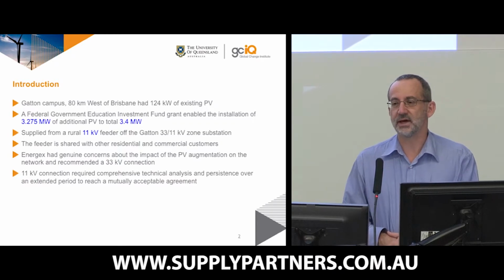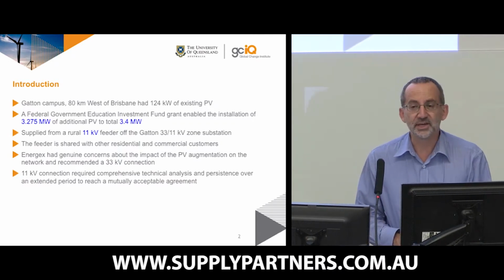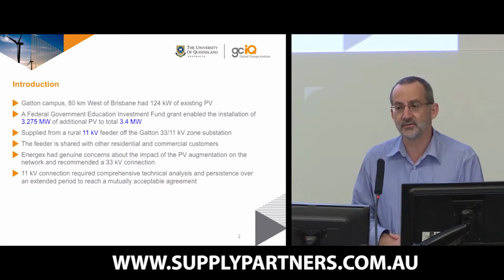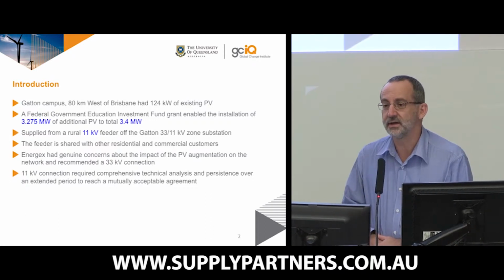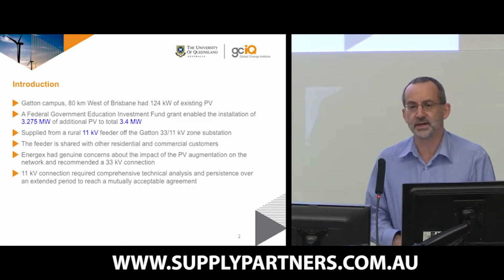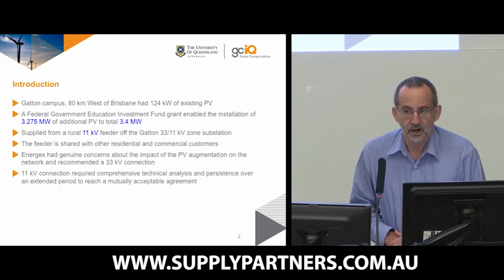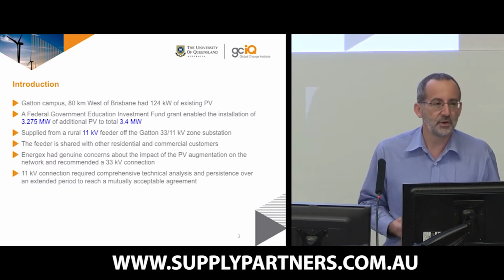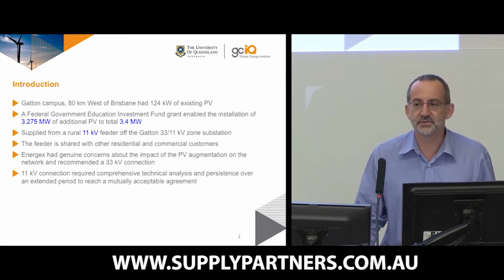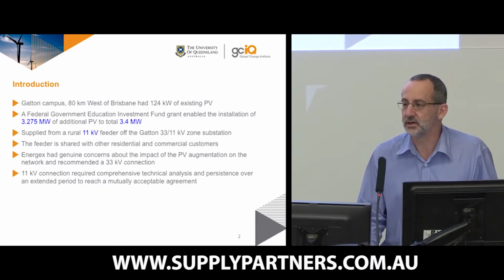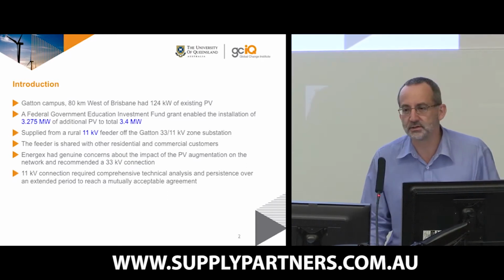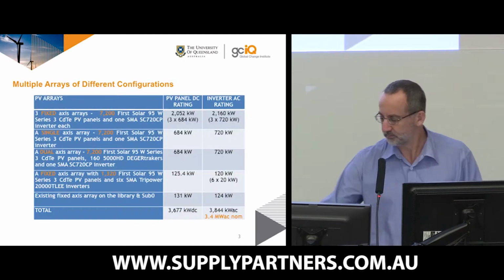It's connected on the 11 kV grid, and that was one of the big issues for us. Energex were a little bit uncomfortable with connecting at 11 kV. They wanted a 33 kV connection, and I'm well aware that many of you have faced enormous challenges getting connections for small systems. I can tell you it was quite a big challenge to get a connection at 3.3 megawatts.